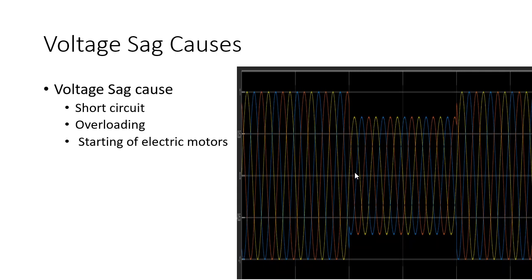This is the output from my oscilloscope scope of the simulating model — I will explain the simulation model in my next video. When my nominal voltage was 100 volts, after time t equal to 0.2 seconds my system faces a dip of roughly 20% in the voltage. After t equals 0.4 seconds the voltage gets back to the nominal value — that is voltage sag.